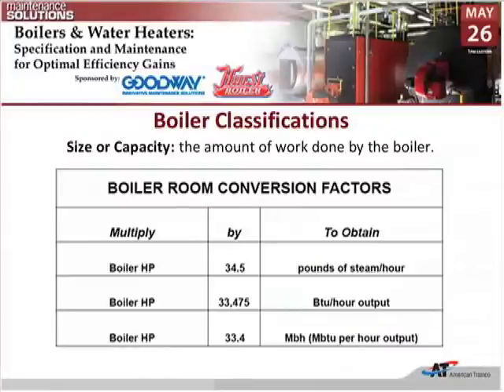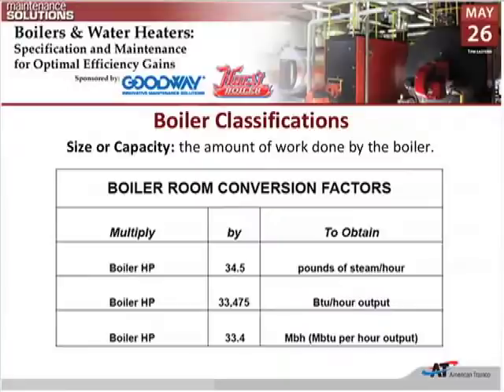Personally, I concentrate more on my thermal efficiency — what am I actually getting for what I'm paying for? Whenever we're talking about boiler horsepower and its output, that is based off of the ASME designation that this boiler is designed roughly for 80% thermal efficiency.